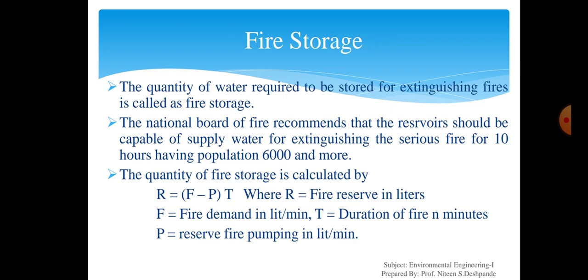Second type of storage is called the fire storage. The quantity of water which is required to be stored for extinguishing fires is called a fire storage. Okay. The National Board of Fire recommends that the reservoirs should be capable of supplying water for extinguishing a serious fire for 10 hours for a population of 6,000 and more. So, this is the minimum requirement of the fire storage for a town of population more than 6,000 people.